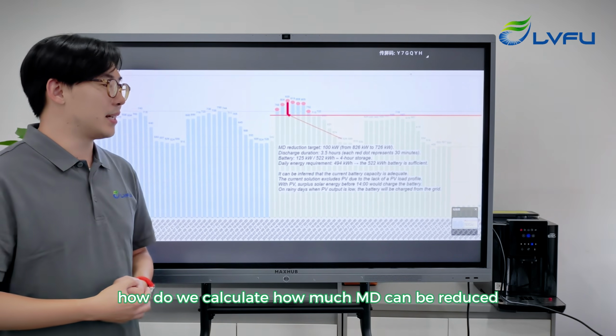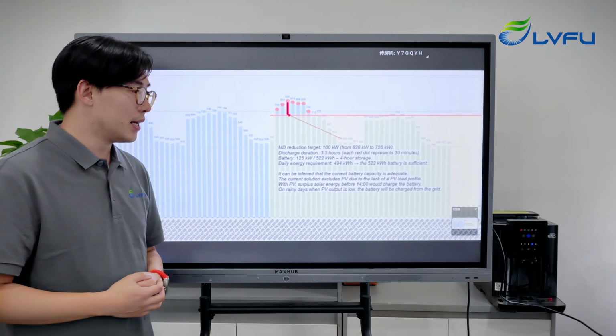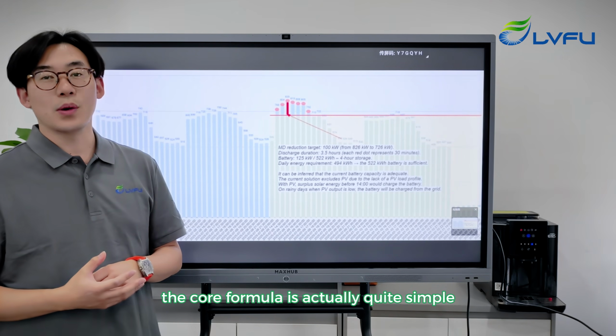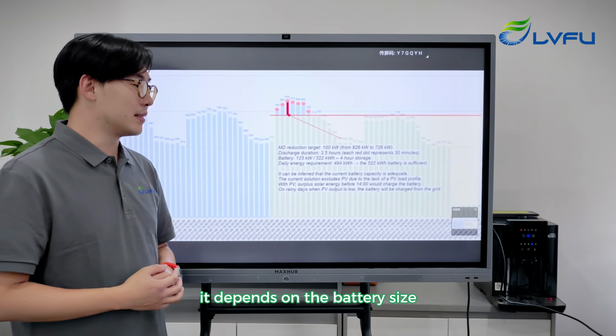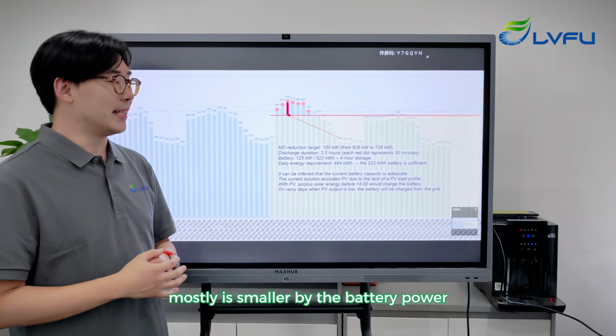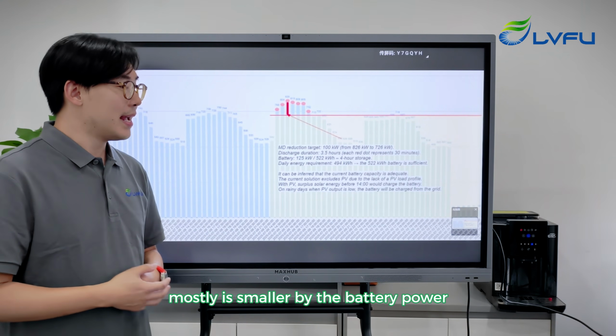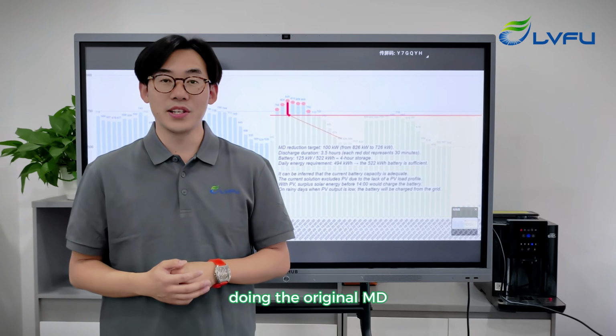How do we calculate how much MD can be reduced? The core formula is actually quite simple. It depends on the battery size. Mostly it is the smaller of the battery power and the average load during the original MD.